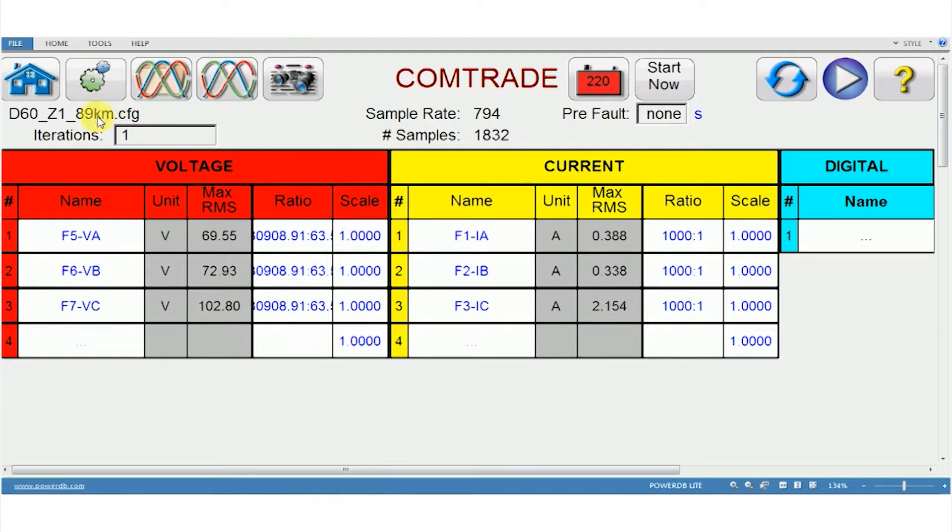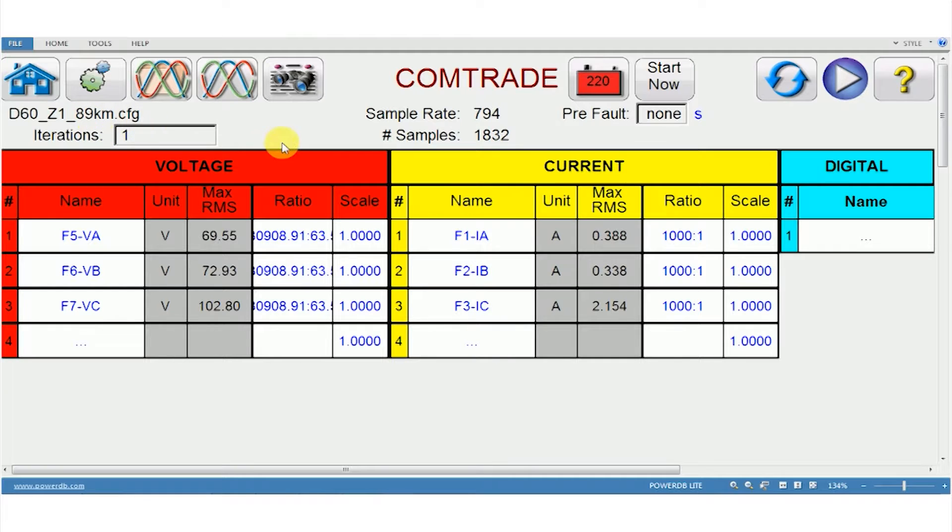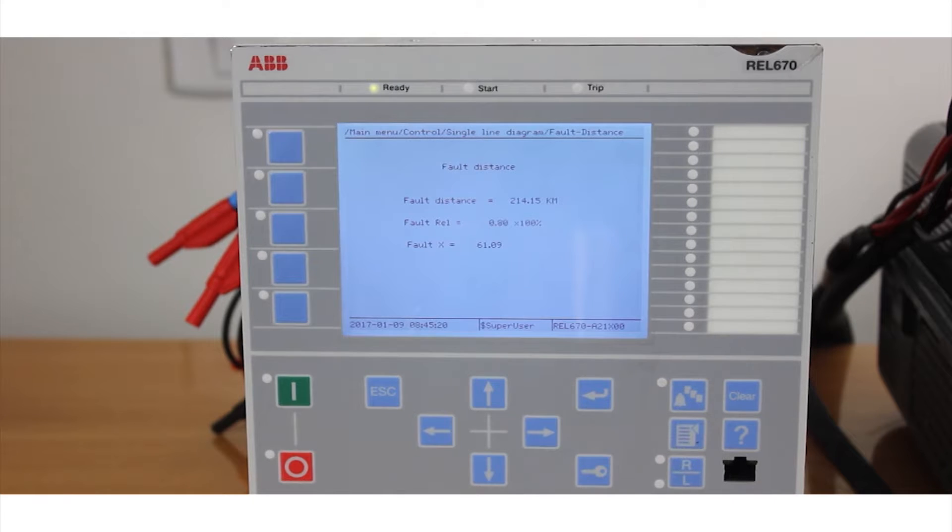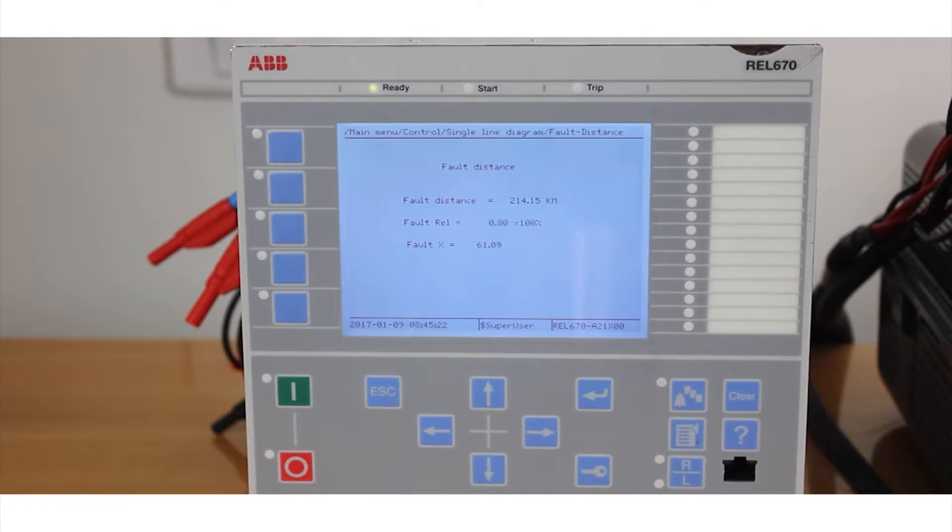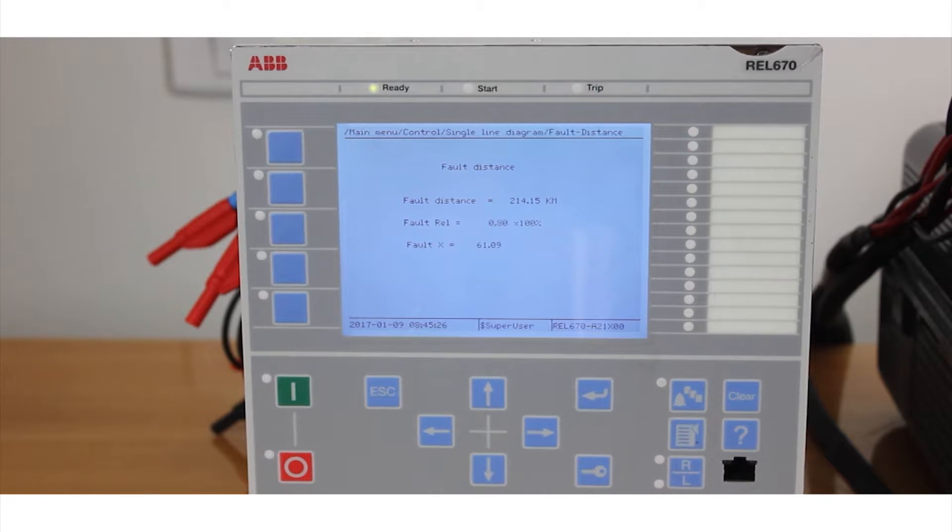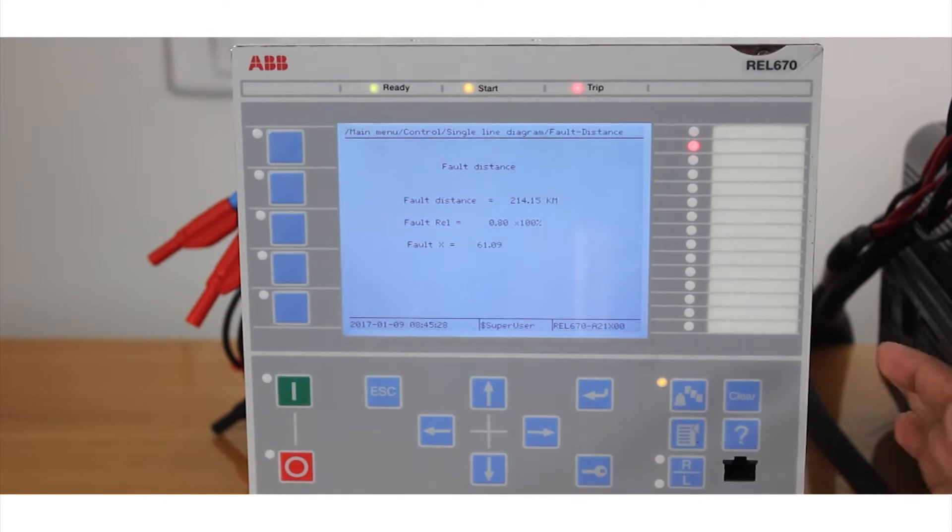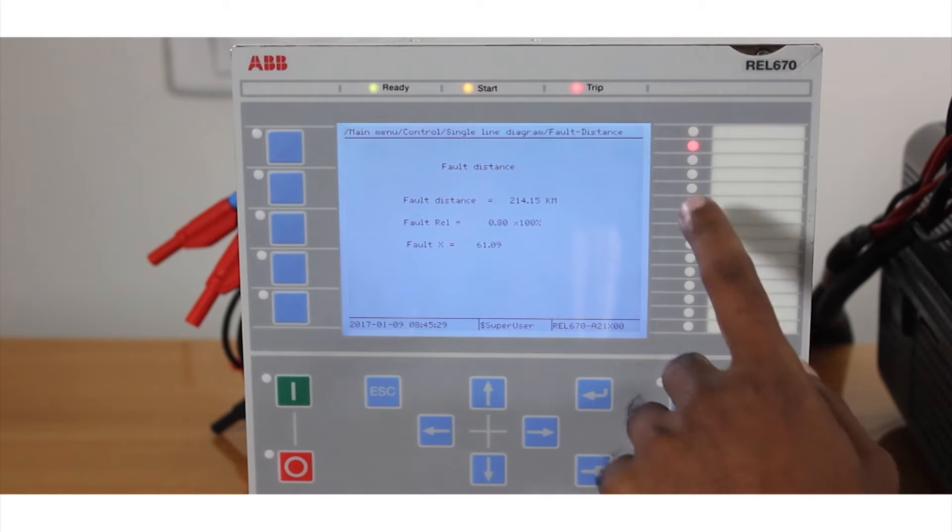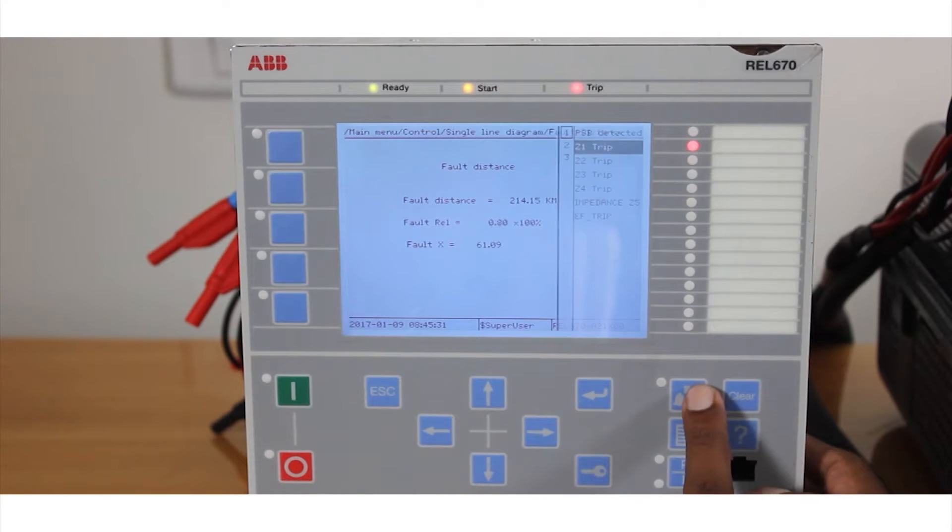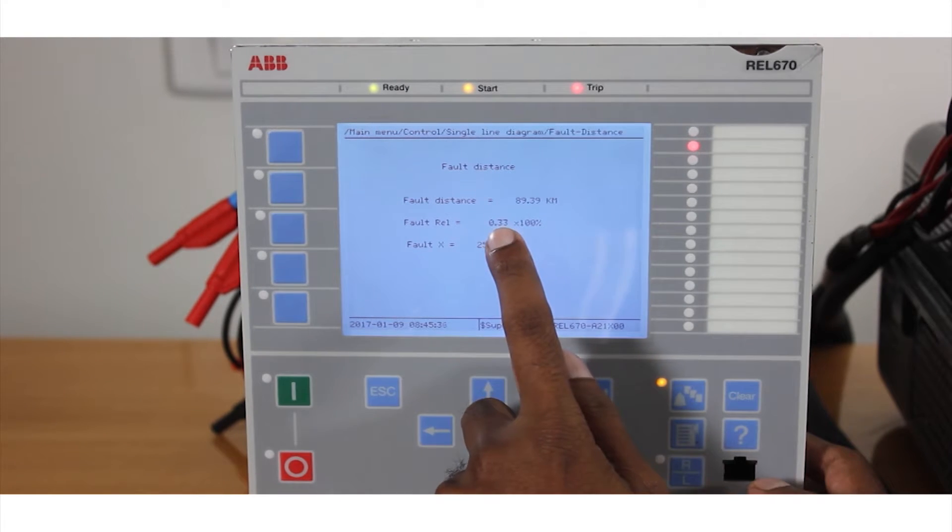Once the three are together you can import it like this. The voltage and current channels are assigned and this is for 89km which was tripped at site. So now I'm going to play back by pressing the play button. I'm just waiting for the channels to get uploaded here and the relay has tripped now. So you can see this LED is for zone 1 and the relay has tripped.